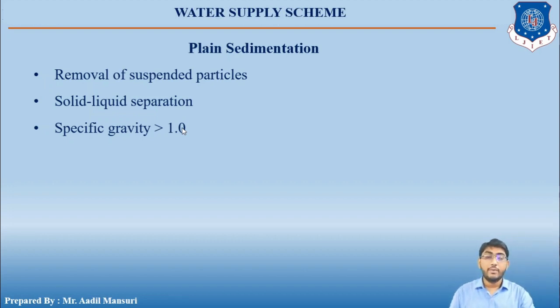Now the basin in which the flow of water is retarded is called the settling tank or sedimentation tank or clarifier, and the theoretical average time for which the water is stored in these tanks is known as the detention time or detention period. Okay, now sedimentation tanks are designed to reduce the velocity of flow of water so as to permit settlement of the suspended solids by gravity.